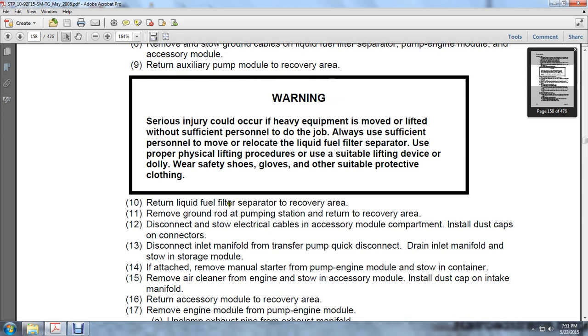10. Return the liquid fuel filter separator to the recovery area. Remove the ground rod from the pumping station and return it to the recovery area. Disconnect the stow electrical cables and accessory module components. Install the dust cap on the connectors. Disconnect the inlet manifold from the transfer pump quick disconnect. Drain the inlet manifold and stow in the storage module.